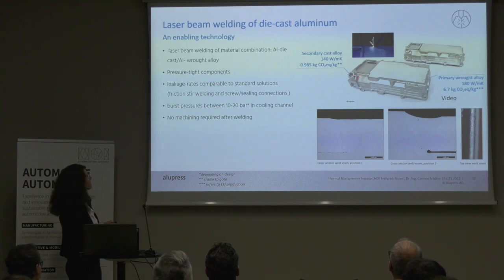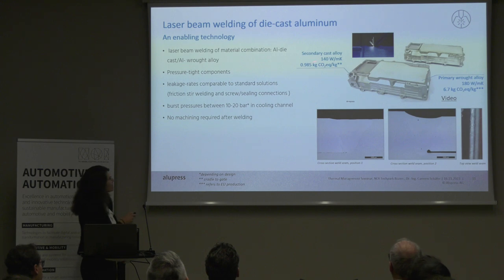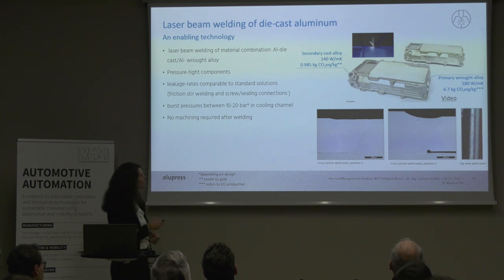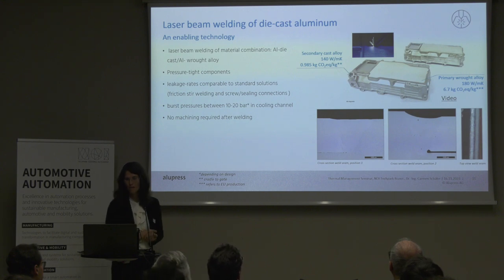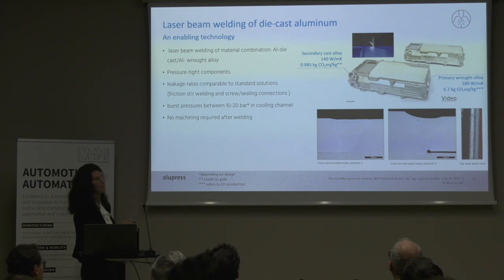With laser beam welding, you also have the CO2 footprint that comes with the secondary alloy, and its heat conductivity is pretty bad. On the other side, what's usually used in liquid cold plates is a primary alloy, a wrought alloy, which has a very bad impact on CO2 but has very nice heat conductivity.